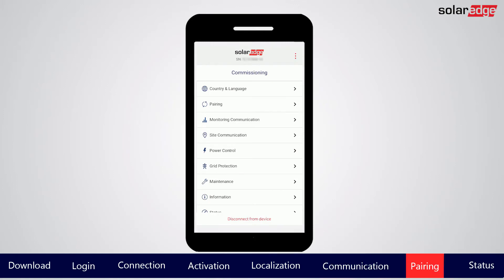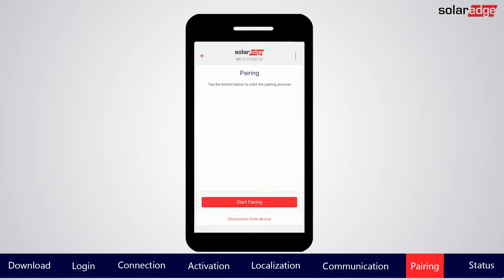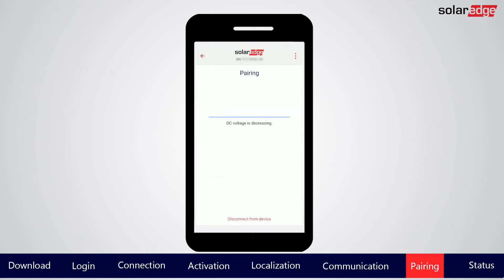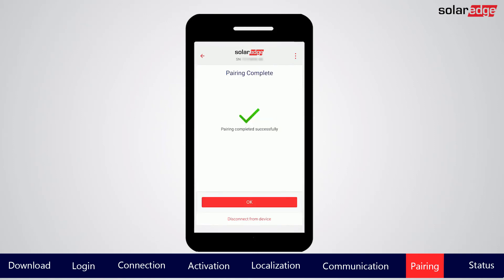Next, we'll pair the power optimizers to the inverter. The power optimizers will not start producing power until they have been paired. Pairing must be performed when the solar array is in good sunlight. From the main menu, select Pairing, then tap Start Pairing. Pairing will take a few minutes. During that time, you can go back to the main menu and perform other configurations. When Pairing Complete is displayed, tap OK to return to the main menu.